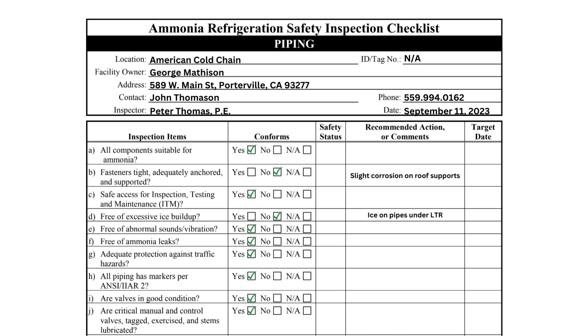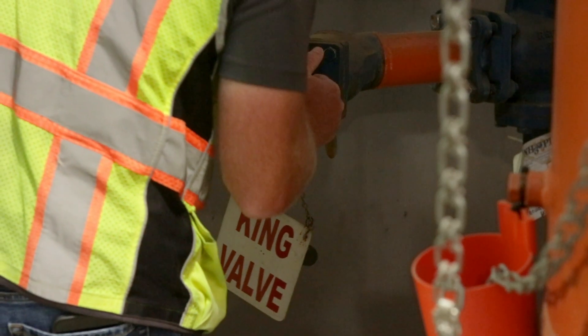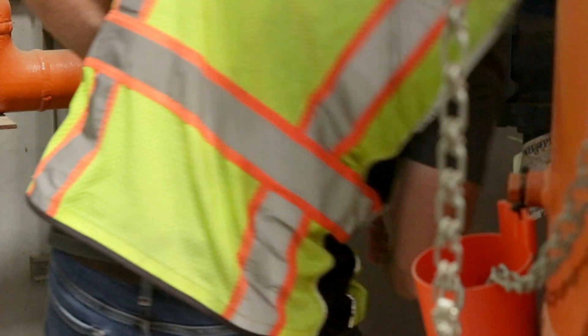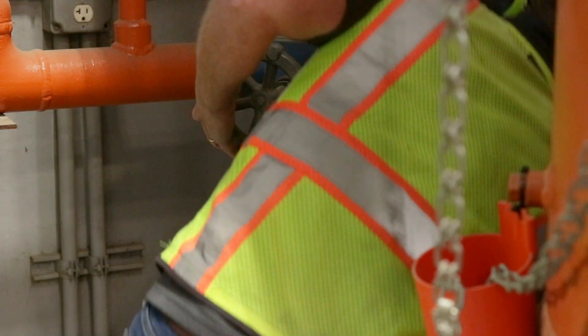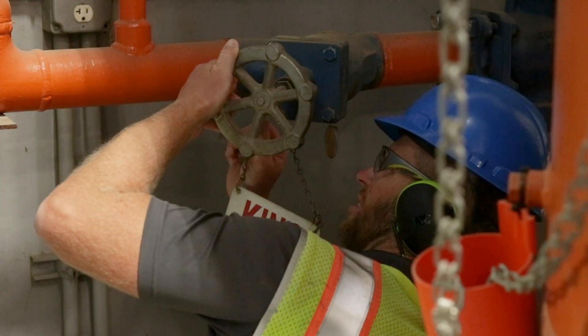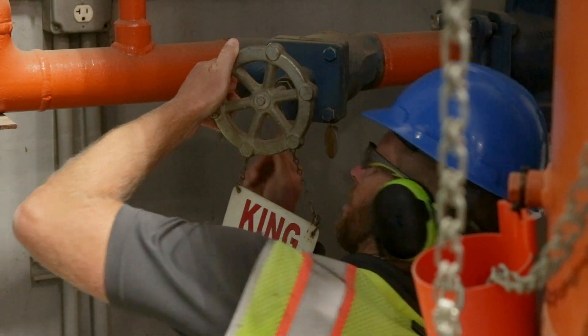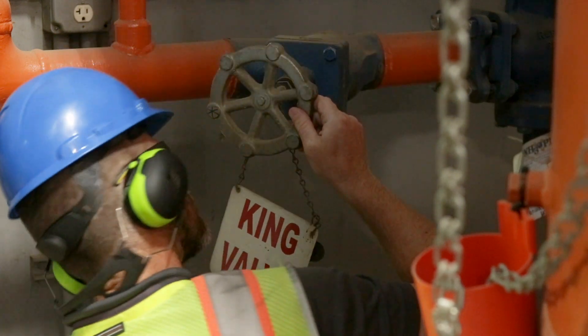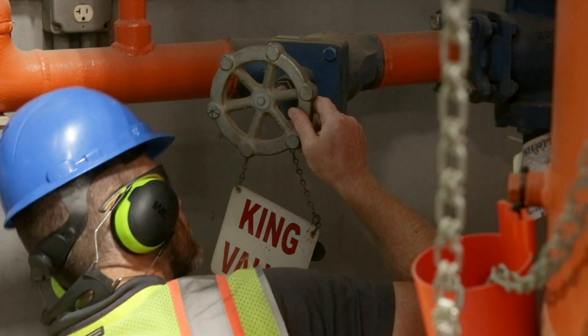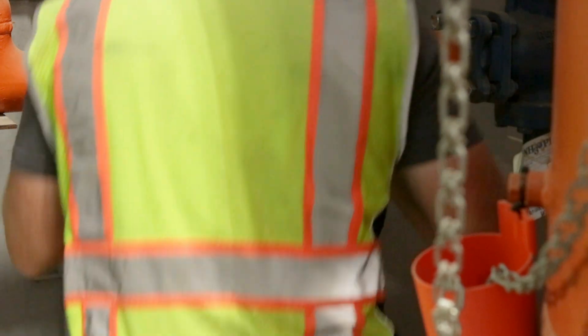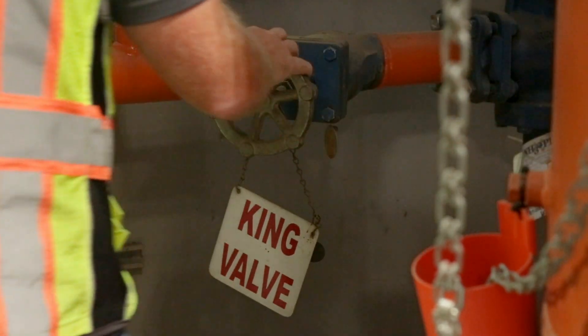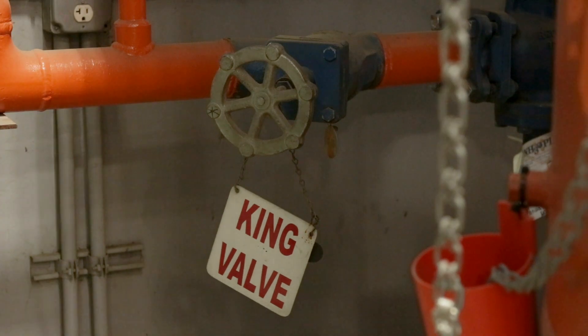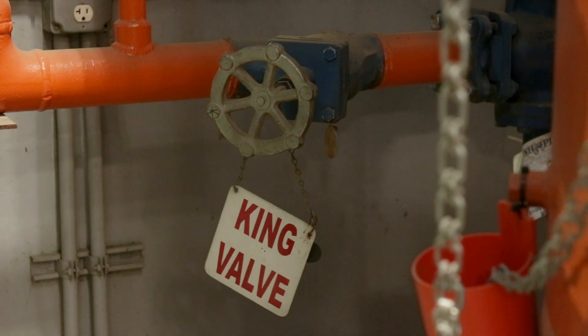Items I and J pertain to the valves associated with the process. All valves should be visually inspected. Deficiencies that should be recorded include corroded or painted stems, missing hand wheels, damaged seal caps, or excessive valve body corrosion.